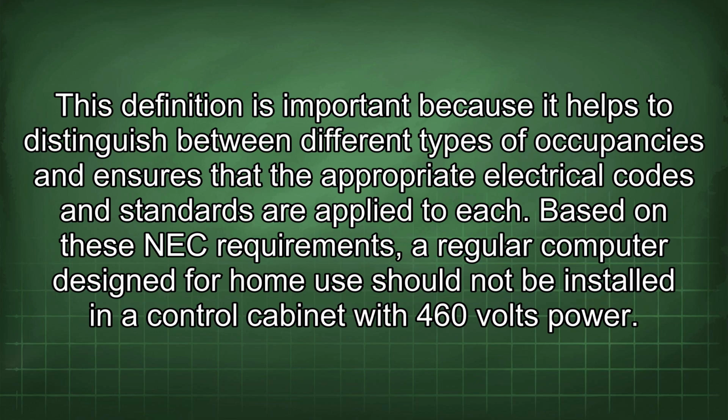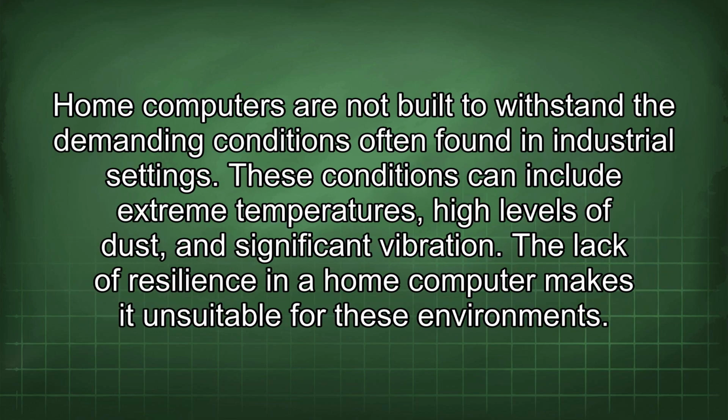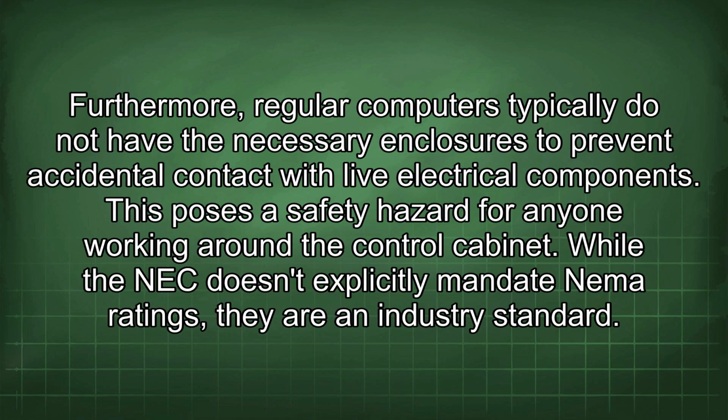Based on these NEC requirements, a regular computer designed for home use should not be installed in a control cabinet with 460 volts power. Home computers are not built to withstand the demanding conditions often found in industrial settings. These conditions can include extreme temperatures, high levels of dust, and significant vibration. The lack of resilience in a home computer makes it unsuitable for these environments. Furthermore, regular computers typically do not have the necessary enclosures to prevent accidental contact with live electrical components. This poses a safety hazard for anyone working around the control cabinet.